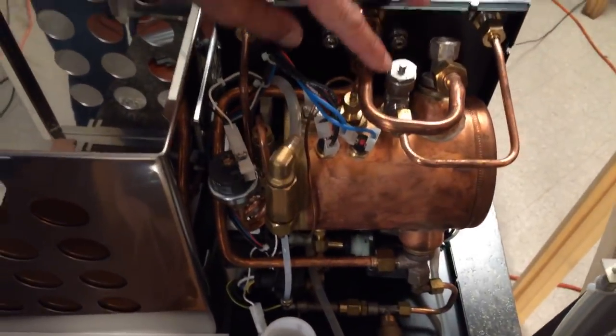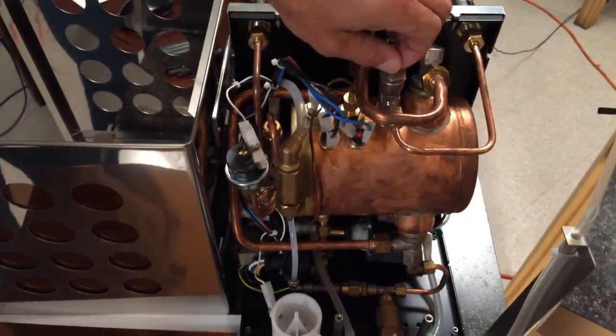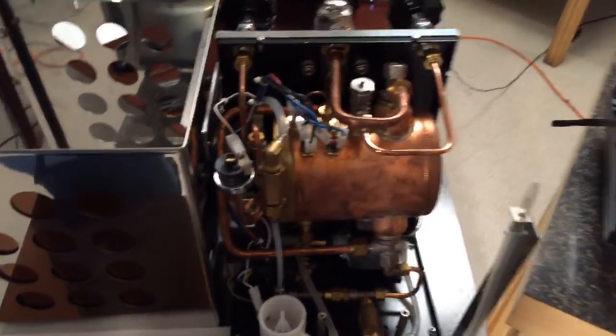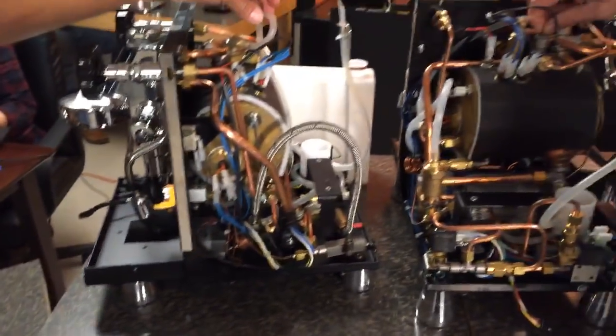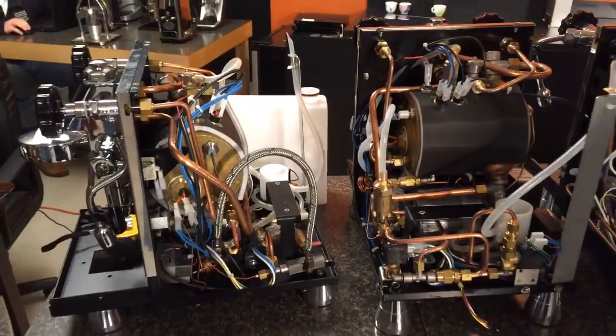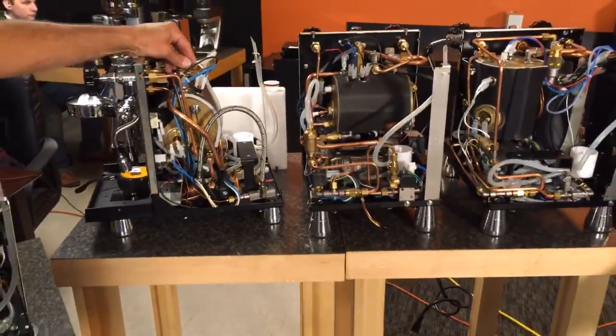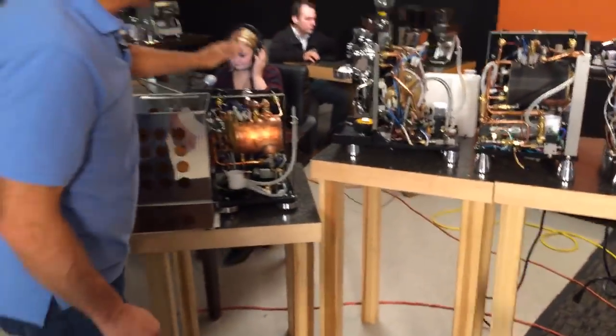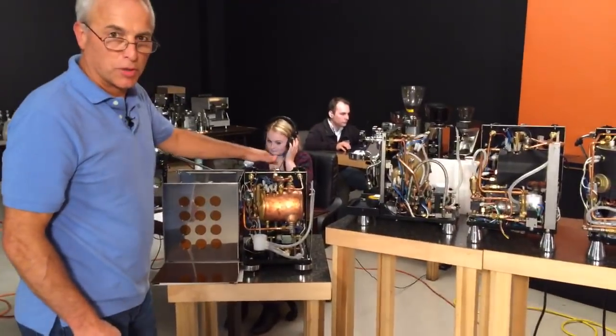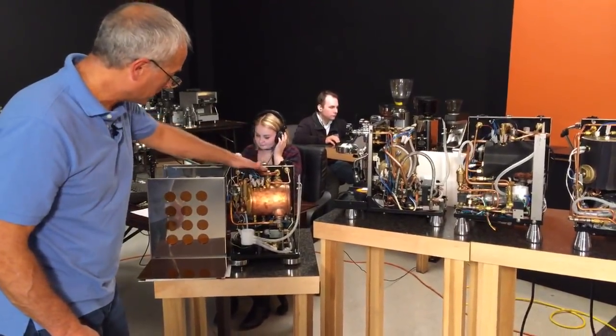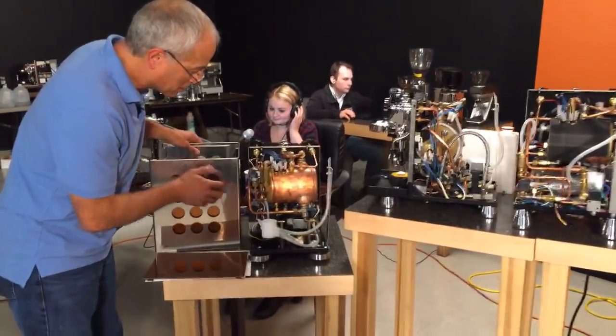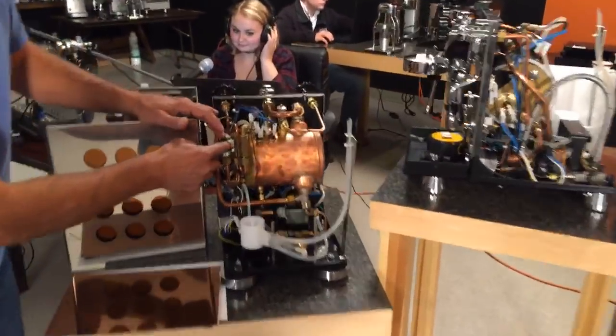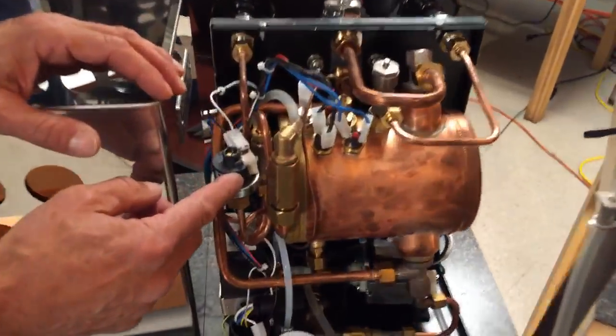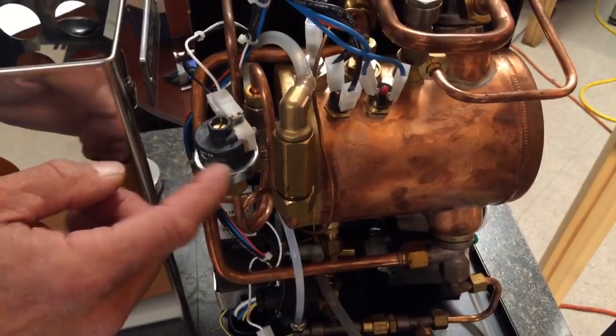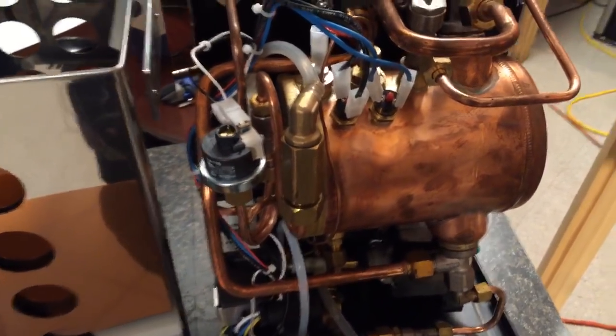Now, the difference between this one and some of the other machines is this one can vent into the housing. The rest of these have tubes on top of them. So I know some of you are probably wondering what that means. I don't want to get into too much depth, but that closes after the boiler heats up, and it seals. The nice thing about this machine is the pressure stat, this is the only one that has a pressure stat. The others are PID, which is a really nice electronic type control. It's a low voltage one, so we expect that to last a very long time.